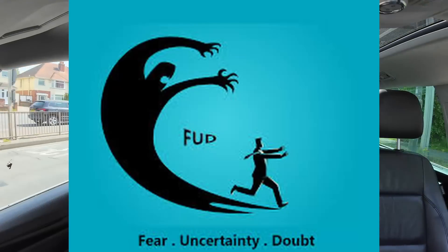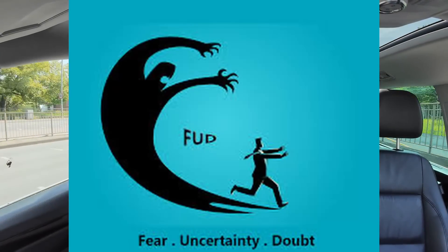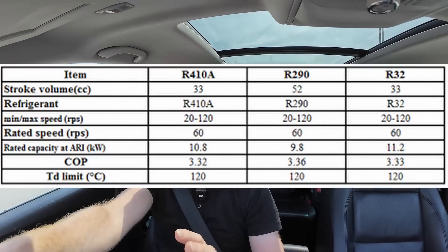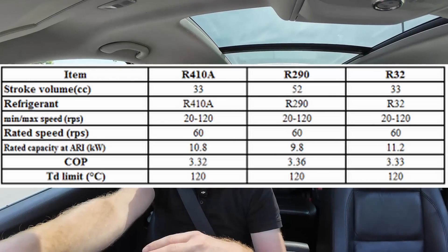So why did they come up with this term of high temperature heat pumps? It was quite clear from their market research and focus groups that people were afraid a heat pump wasn't going to keep them warm in their houses. So they jumped on the initiative to start calling these heat pumps 'high temperature heat pumps' to try to differentiate them from the previous generation. In reality, R32 and R290 are both equally efficient — you're going to have the same COP and the same SCOP.